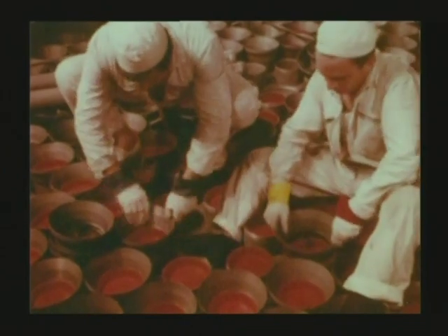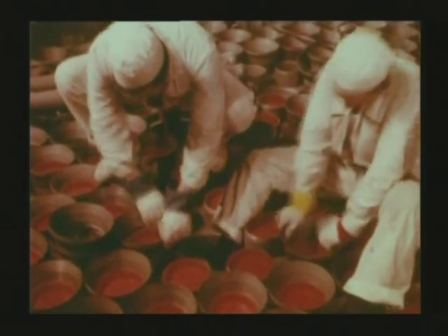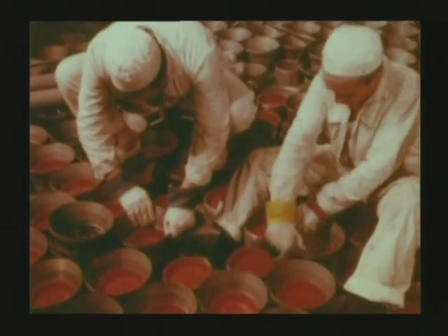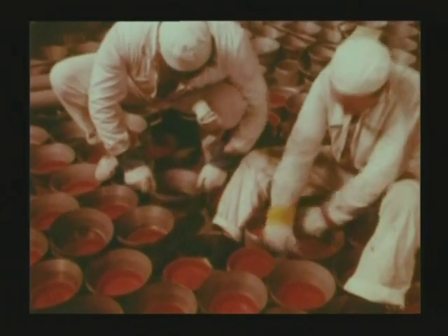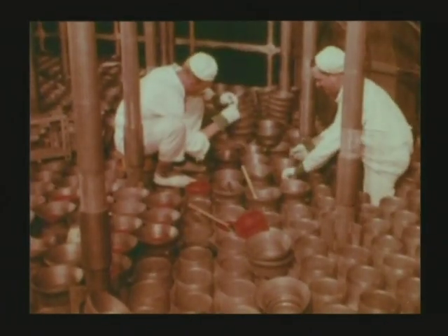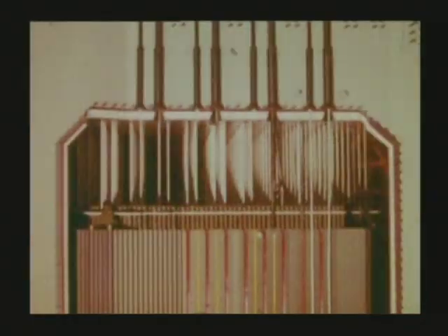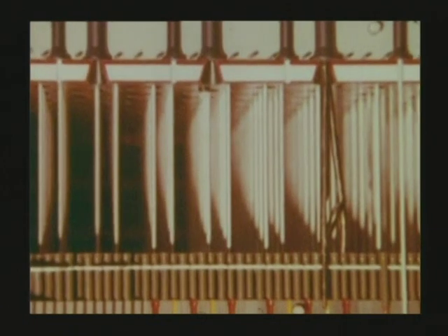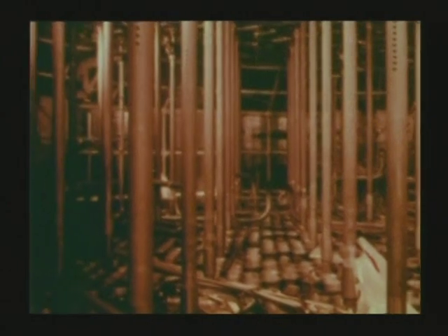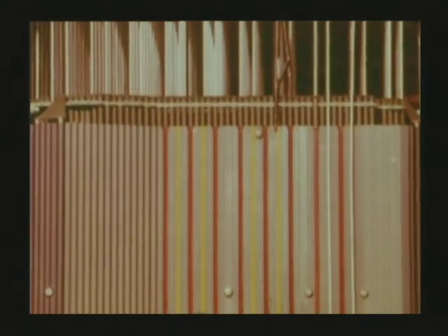In order to facilitate the loading of the fuel elements, the mouth of each channel is topped by a tapered funnel. At the top of the stack are located the guiding devices for the 135 control rods. Inside these shafts, boron carbide rods suspended by cables and moved by an electric hoist hang down in some of the core channels as a means to regulate the output.